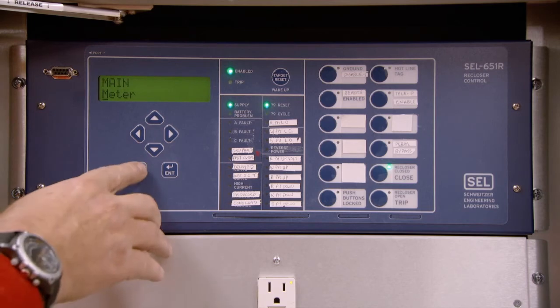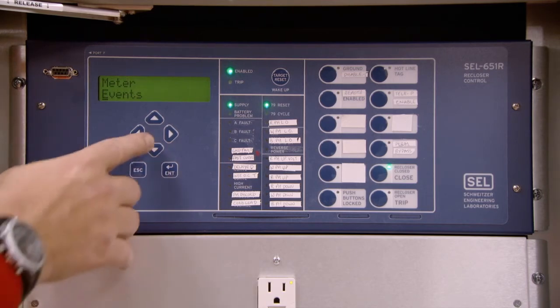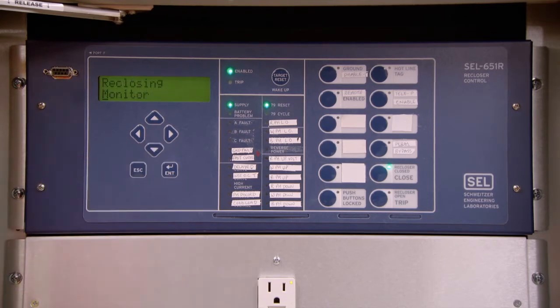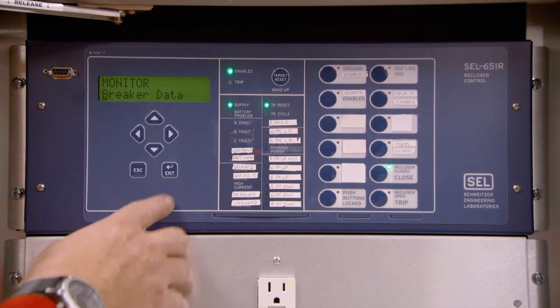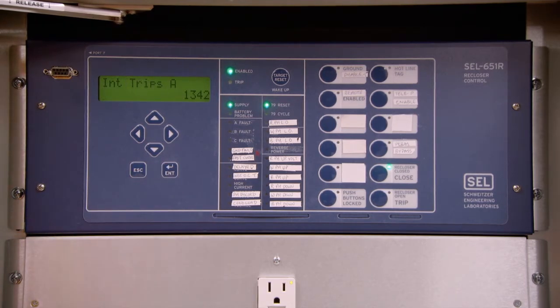If we press Enter, and then the down arrow, we arrive at the Meter Events submenu. Pressing Enter on the Reclosing Monitor menu will take us into Breaker Data. Pressing Enter again will indicate the amount of internal trips on the A phase. If this unit were out in the field, this screen would indicate the amount of trips that this unit has actually gone through. In our testing procedures, you can see that we have gone through quite a few. Pressing the down arrow again shows us the current applied on the A, B, and C phases.